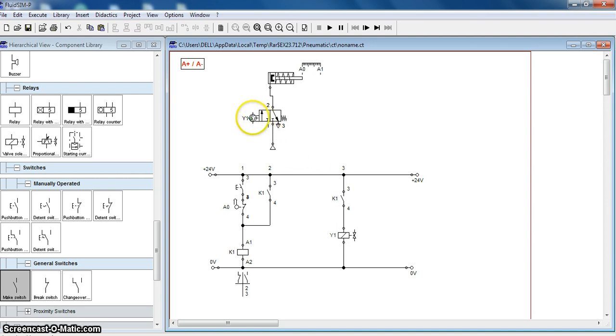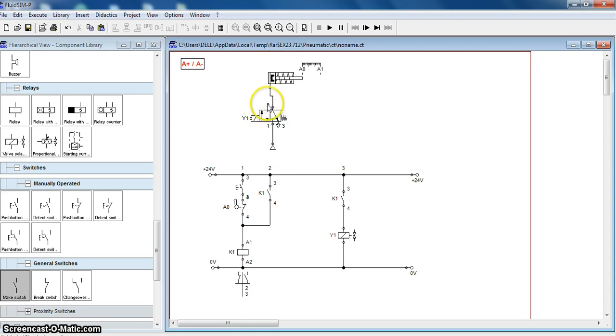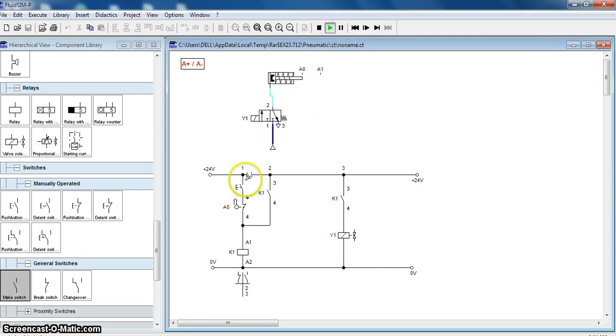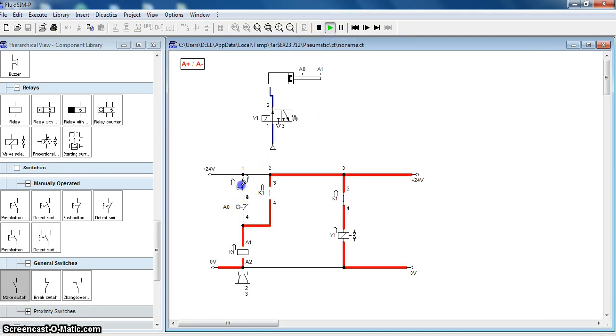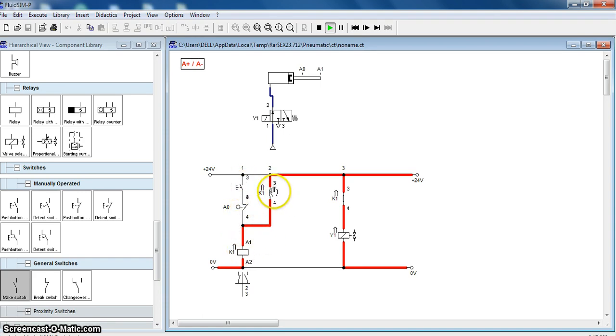When Y1 is energized, the valve moves in this direction and fluid flows from port 1 to port 2, and the cylinder moves forward. When the start button is pressed and then released, K1 remains charged because of the latch. As K1 is charged, Y1 is charged. As solenoid Y1 is charged, the spring is not able to take its action, and the cylinder extends to position A1.